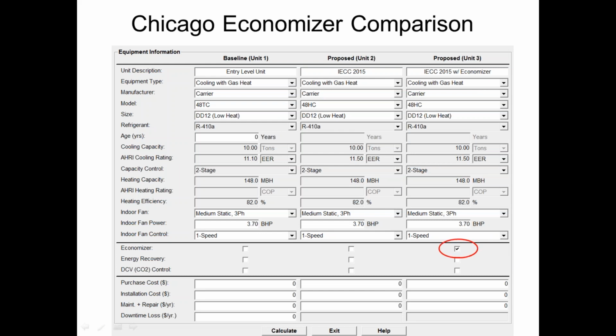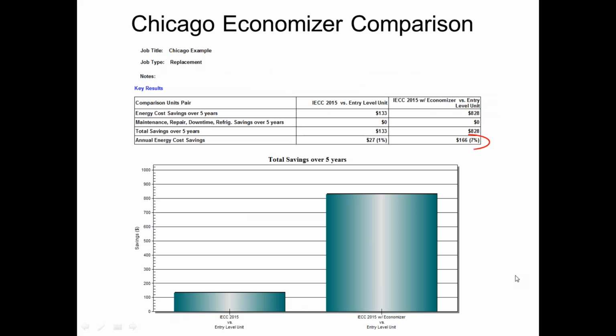All right, if we're using our same little software tool over here, we got our entry-level unit in column 1, we got our code unit in column 2. Now column 3 is a code unit, plus I check the box saying that I have an economizer. Everything else is absolutely identical, right? So I'm saving 1% energy in Chicago from going from an entry-level unit to a code unit. I'm saving 7% if I go to a code unit with an economizer. So the economizer's got a pretty decent cost savings associated with it. Yeah, it's only $166, but this is only a 10-ton unit. Obviously, the bigger the unit gets, the more dollar savings I'm going to have.